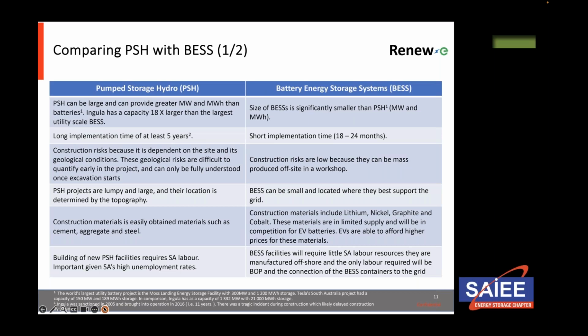Unfortunately, pump storage has a long lead time. Battery storage you can have up and running within 18 to 24 months. There's construction risk with pump storage since it's dependent on the site and geological conditions, and it's really difficult to quantify the geological risks until you've started excavation, so there's a risk component of how much it will actually cost. In the case of batteries, there's limited construction risk because they're mass produced in a workshop in a controlled environment. Pump storage projects are large and lumpy, and location is determined by topography, while battery storage is small and can be located where it best supports the grid.